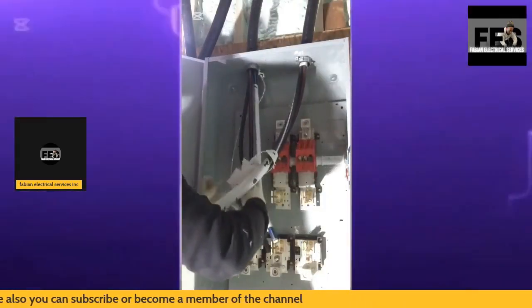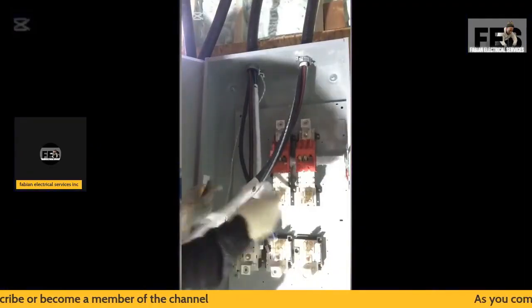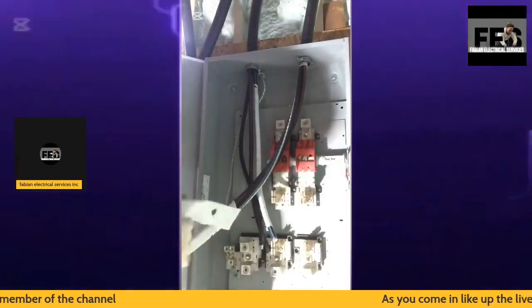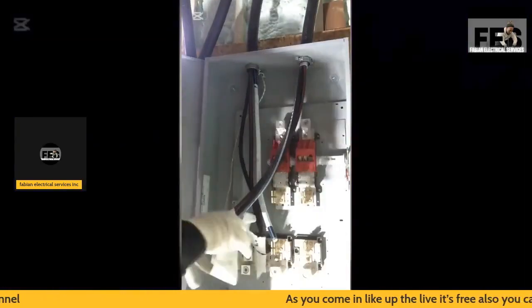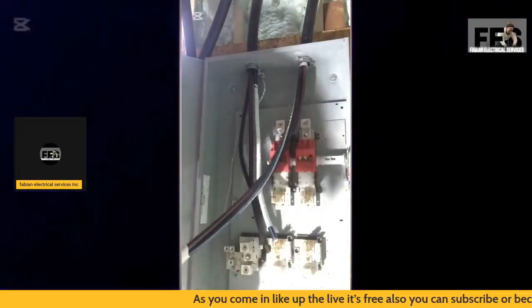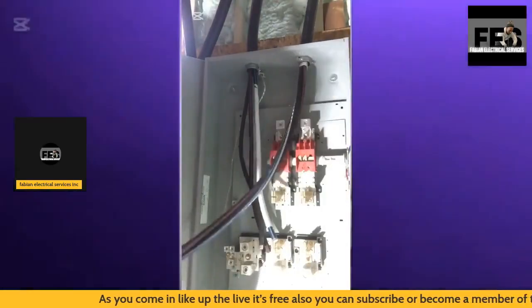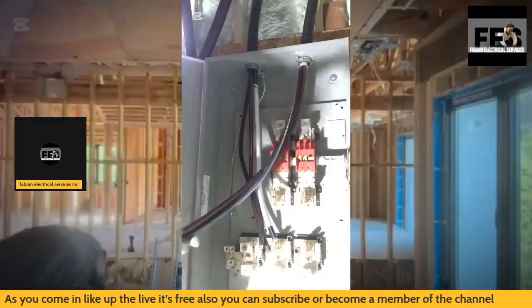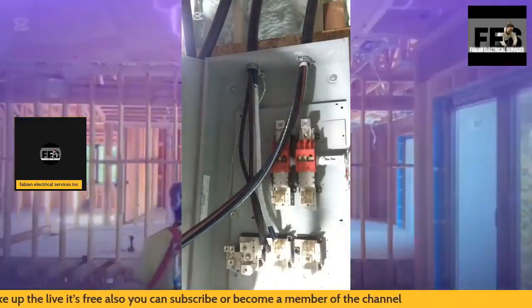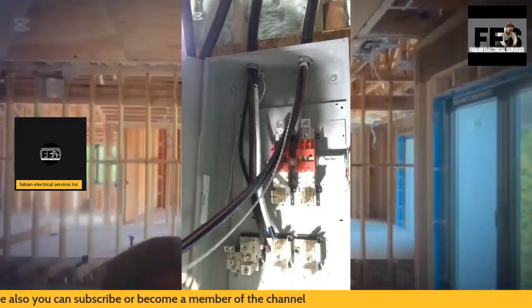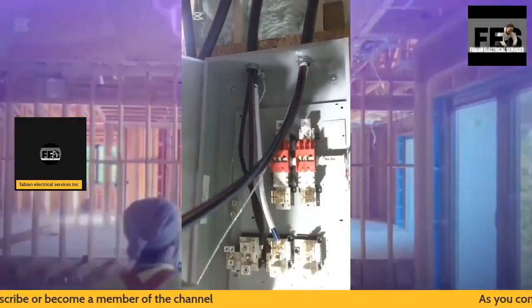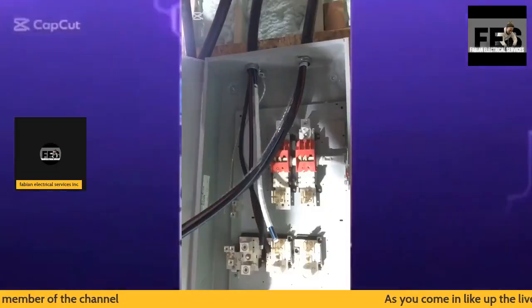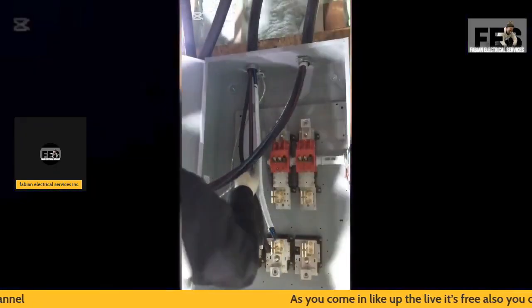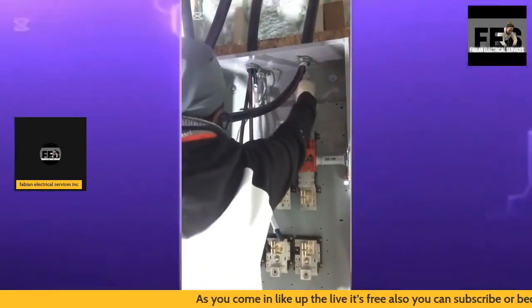The main 400 amp panel is located inside of the electrical room, inside the basement of the home, and it's more than 40 feet away from the meter base. So I have to install my disconnect per code to stay within my electrical code compliance.